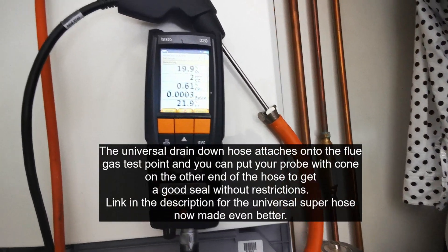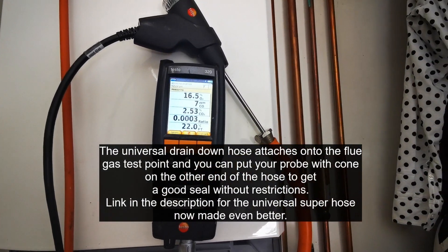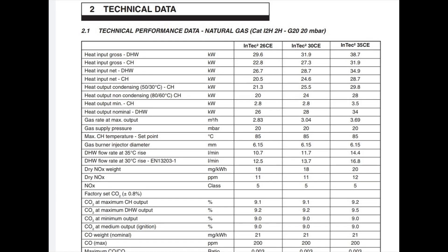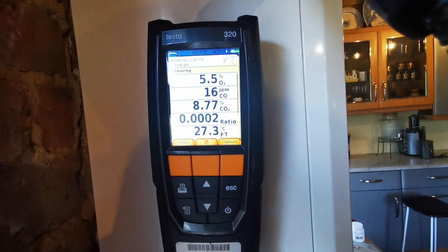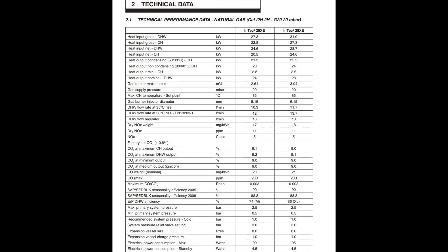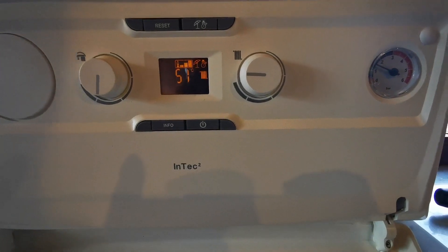Then put your hot boiler into high fire and low fire and check the CO2 readings in comparison with the manual — every output is different. Check that first couple of pages in the manual and it will tell you what you should be getting. CO readings should be below 200. If you don't know how to put this boiler into high fire or low fire, I'll put a link above for the video on that.